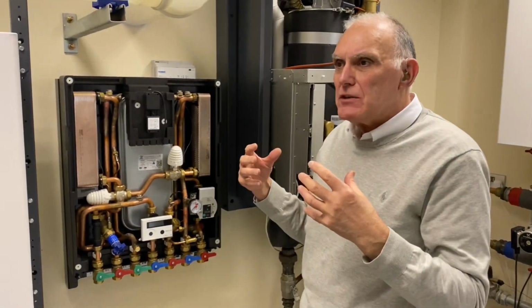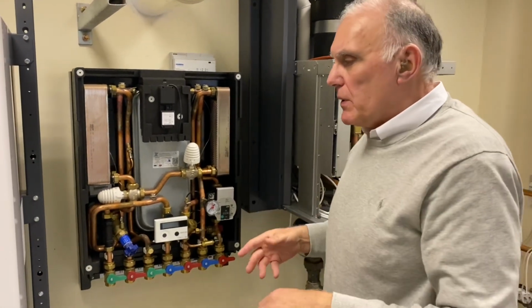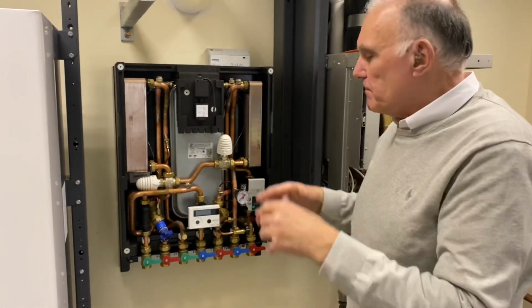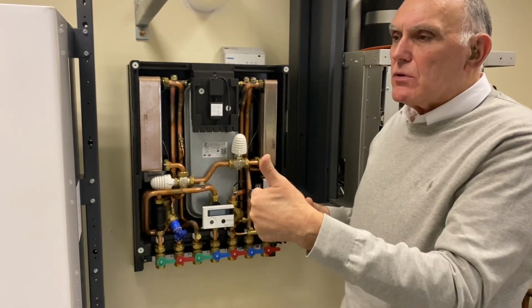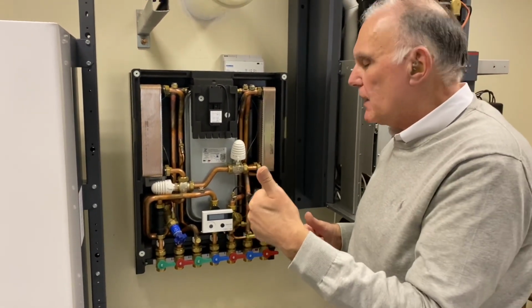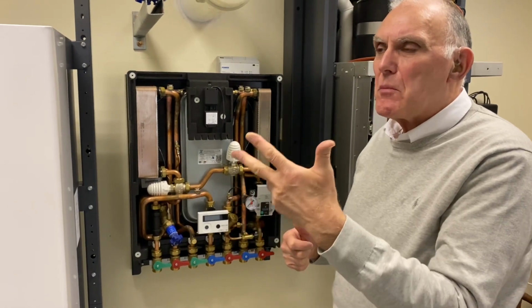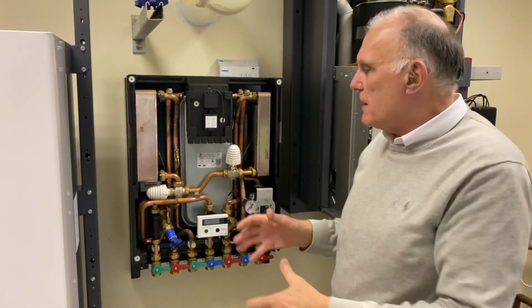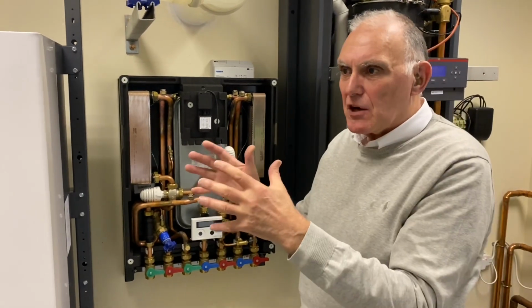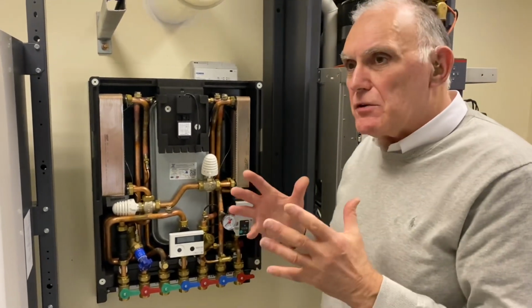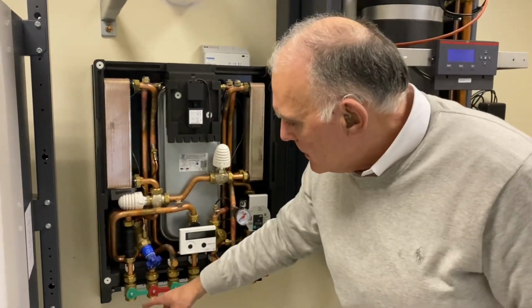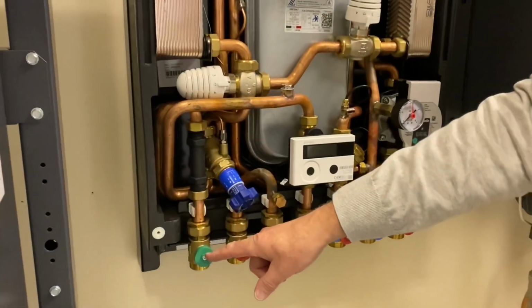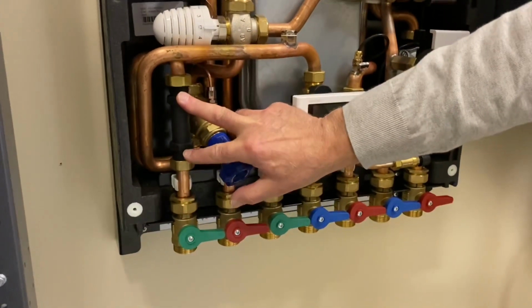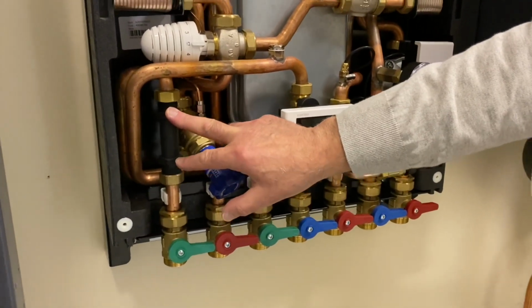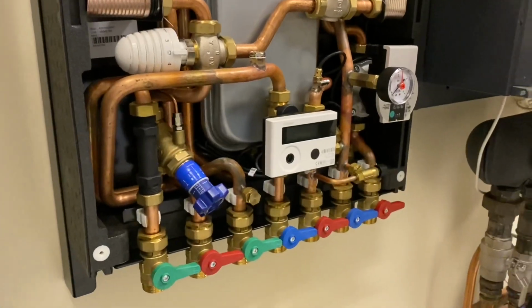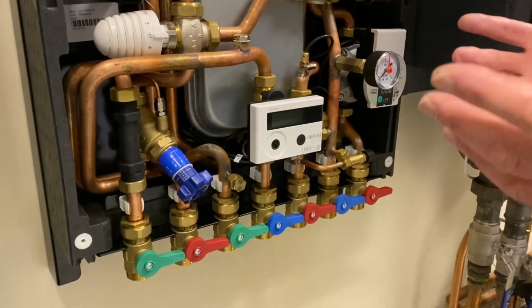So you've got to imagine an apartment block with a pipework duct up it, and there'll be fresh cold water, a primary flow and a primary return to the main plant room. Everything else is done here for that particular apartment or house. If I do the cold water first, domestic cold comes in. There's a spacer here where a water meter could be fitted, so the apartment user, householder, could be billed for the domestic cold water use and hot water use.